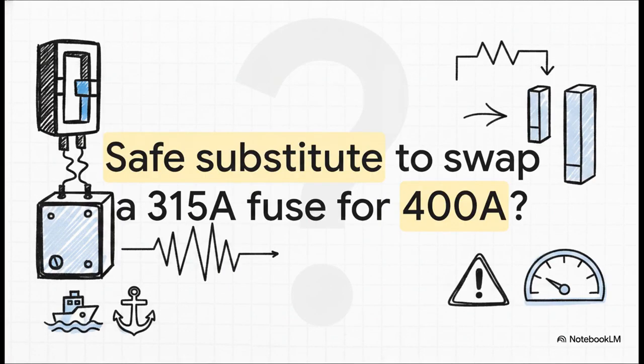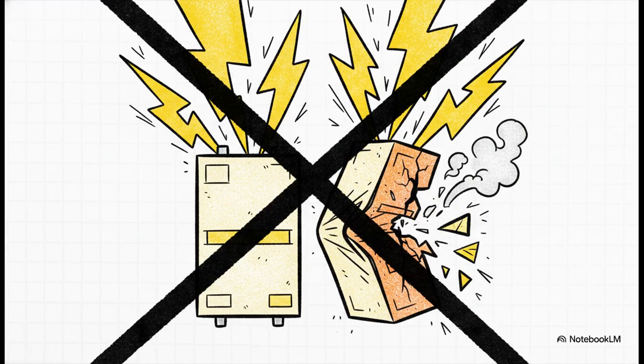Let's throw a real-world curveball at you, something you might actually face during commissioning or routine maintenance. Imagine a spare parts order comes in, and instead of the highly specific 315 amp fuse for your V7/ZC install, somebody hands you a 400 amp fuse. They match in physical size, and hey, the contactor's rated for 400 amps anyway, right? So, is this a safe substitute? Take a second to really think about what we just discussed regarding that protective margin. The answer is an emphatic absolute no.